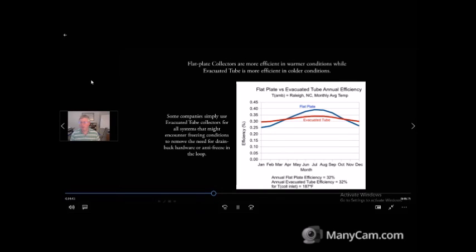Evacuated tube is really a much better option at that point. You can make a trade-off in warm and cool temperate climates. Flat plate typically is going to win in tropics and subtropics, so what you're going to see is that if you're in the tropics or subtropics...